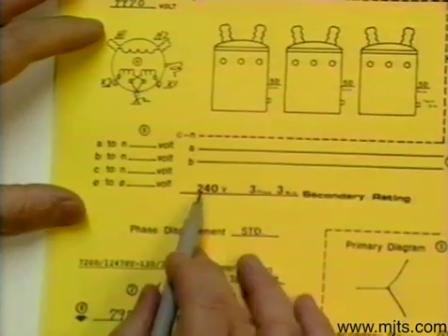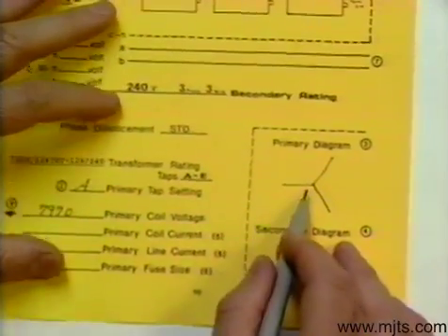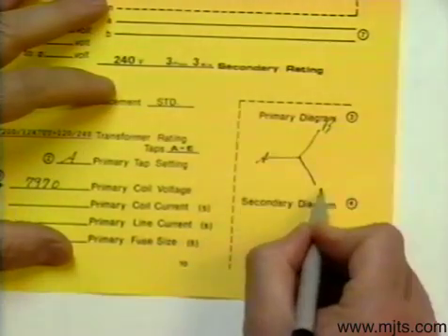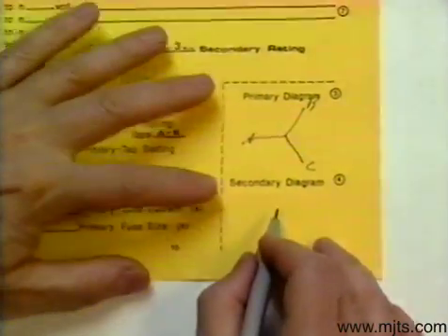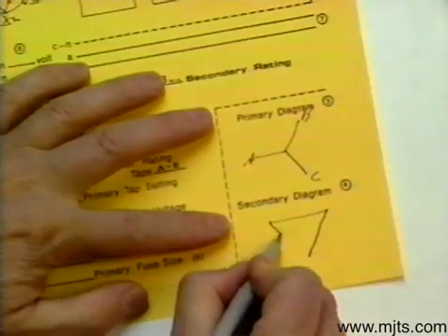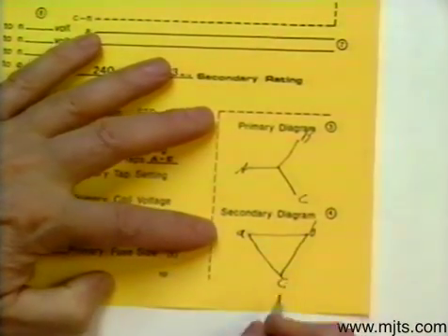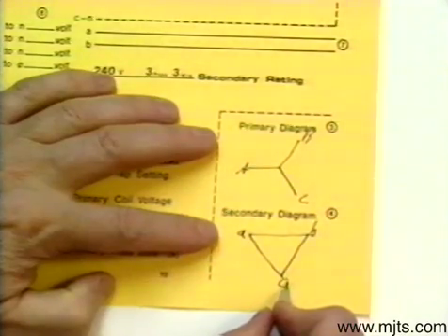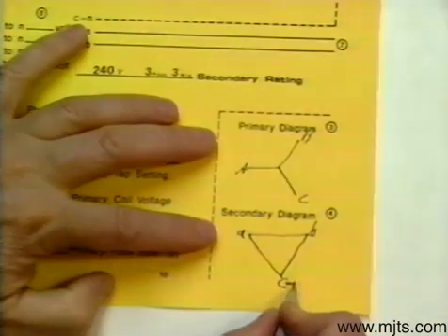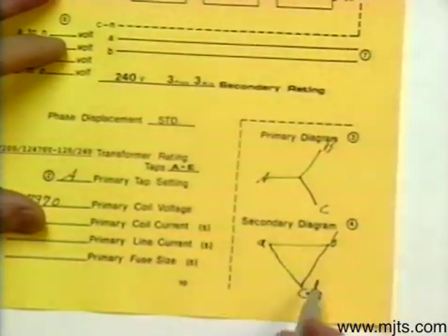On the low side we want delta standard. The least possible displacement on a wye-delta is 30 degrees, so we will have a diagram on the low side that will look like this. Our A phase is going to be at this point, then B and C. Three wire means one of these is grounded, and according to our schematic we have C grounded — and remember that any one of the three could be grounded if desired.